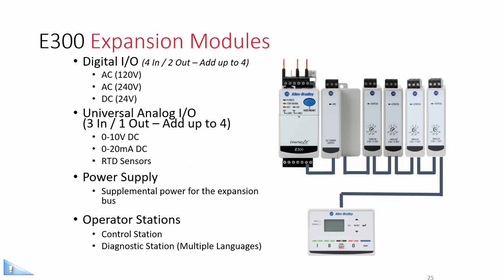We have additional digital and analog I/O modules and operator interface accessories to the base E300 system. There are digital expansion modules. There are 3 types. Again, you just select your voltage. So 110, 120, 220, 240, 24 volt DC. And then you can select up to 4. Only 4 in and 2 out.